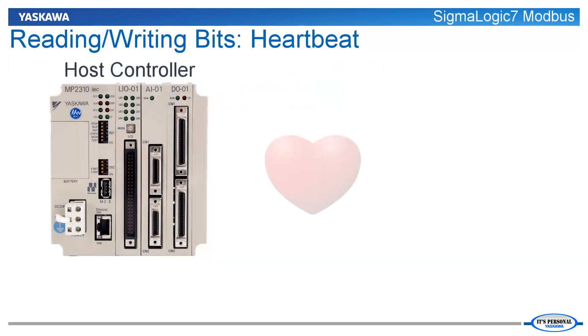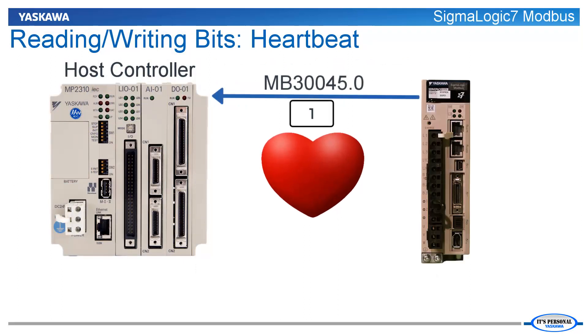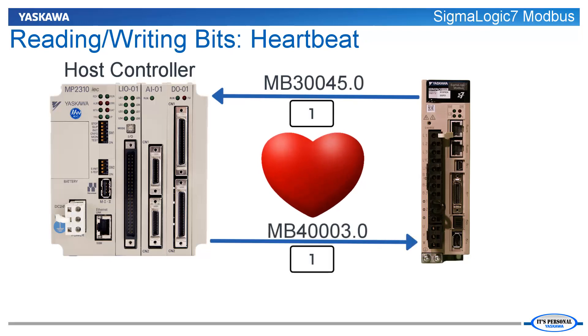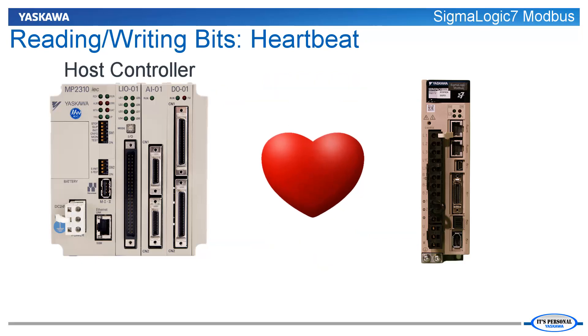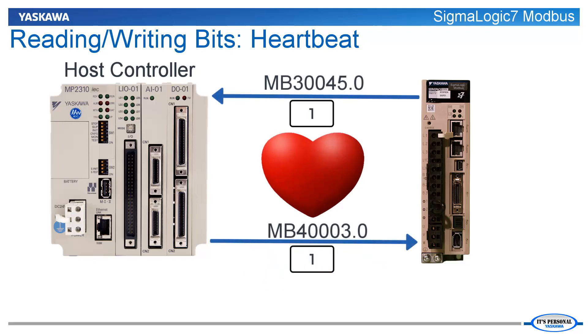It is essential for the host controller to establish and maintain a heartbeat with the Sigma Logic 7 Modbus. This is accomplished by reading register 30045 bit 0 and reflecting that value back to register 40003 bit 0. The heartbeat will normally toggle on and off every 500 milliseconds. If the heartbeat reflection at register 40003 bit 0 does not change state within one second, the Sigma Logic 7 Modbus will automatically stop all motion and disable the servo.